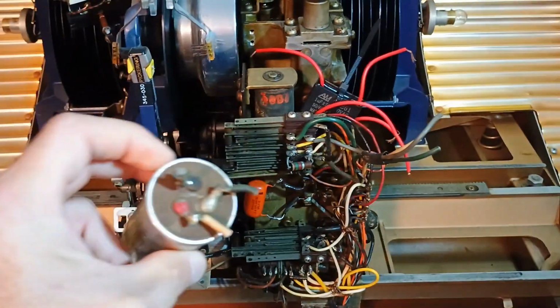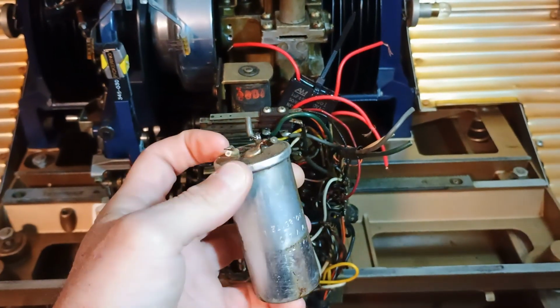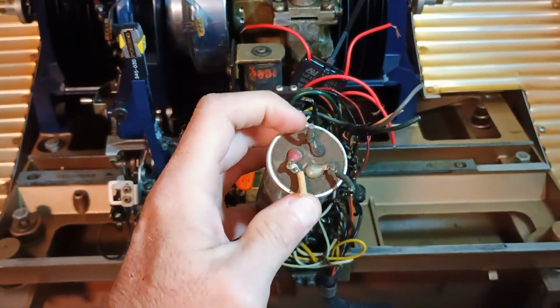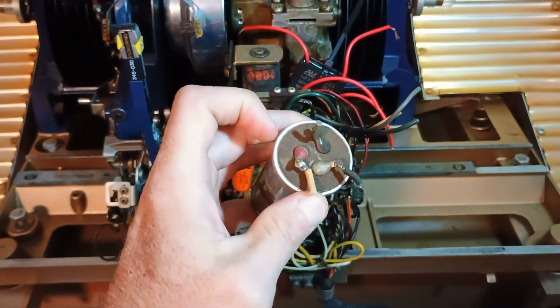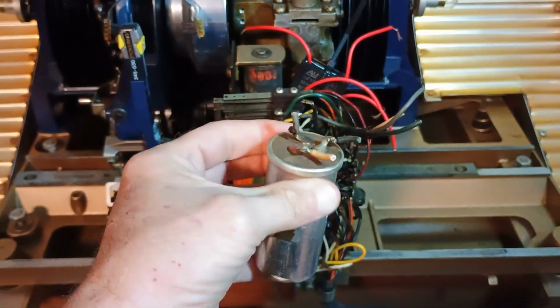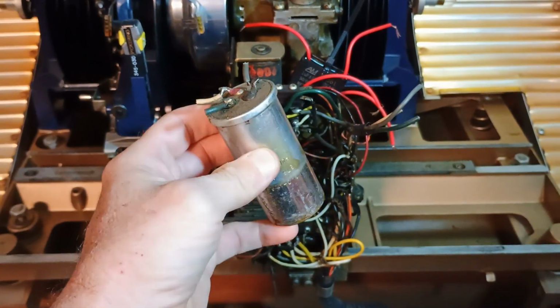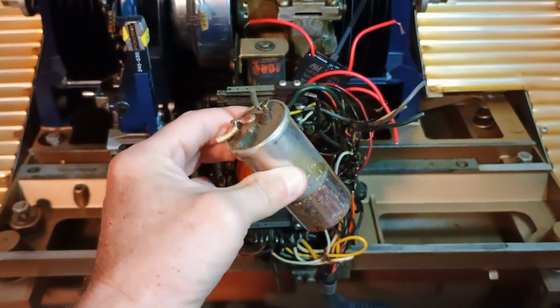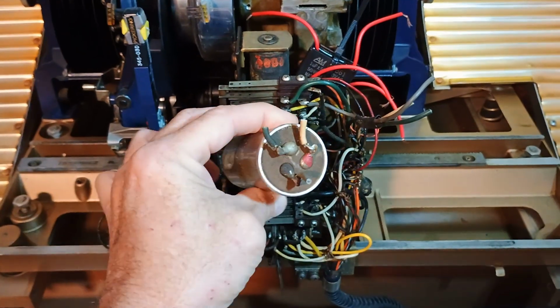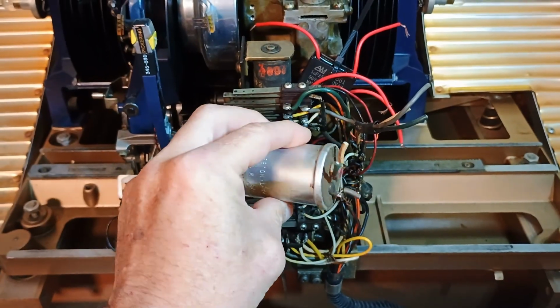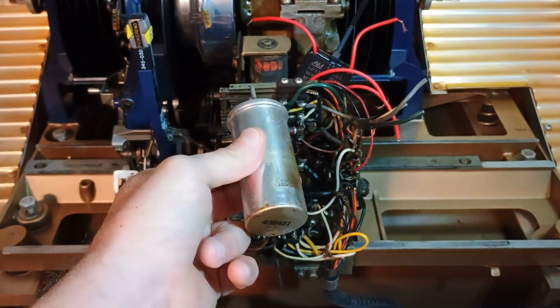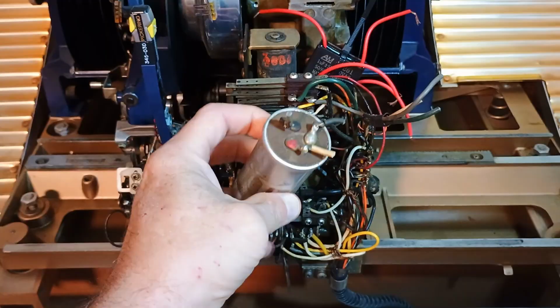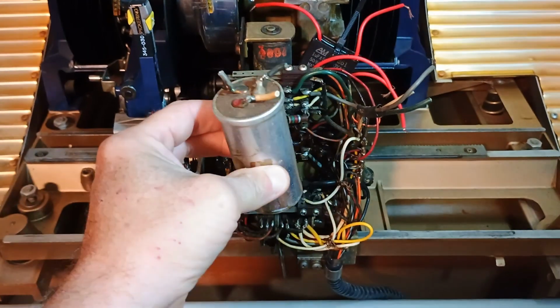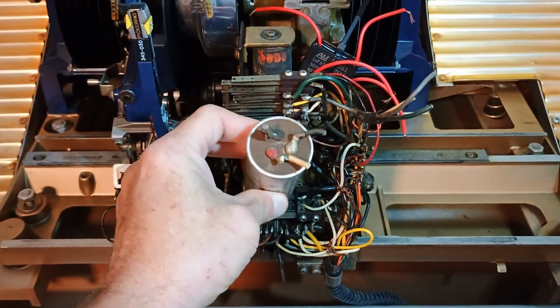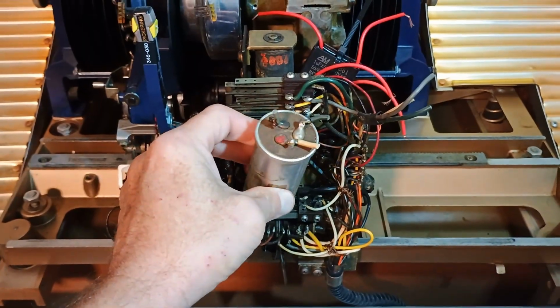So I'm going to set this down. When you do these, make sure the machine's off, and you want to short between all of these terminals with a heavy grade screwdriver. That way you discharge the capacitor to make sure there's no voltage, because this could definitely cause you a problem. If you don't understand that, you should not service something like this, because there are high voltages involved that could harm you or kill you.